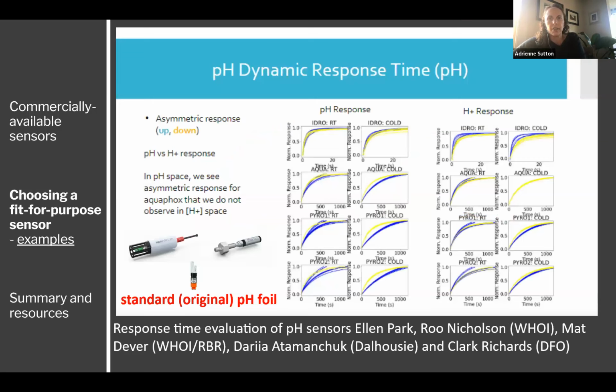Daria and others also tested this for the Pico and also for their standalone sensor version, and found that response time varies depending on temperature, whether the sensor is ascending or descending, and whether you're looking at logarithmic pH values or hydrogen concentration values. pH response in these figures is shown on the left, and hydrogen ion concentration response on the right under the same scenarios, and their response looks different.